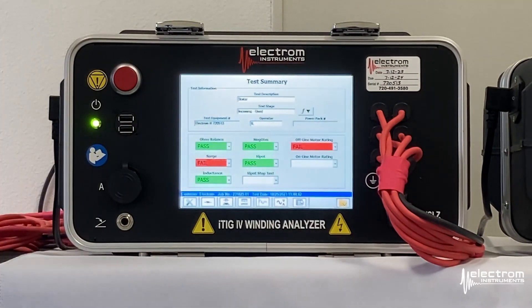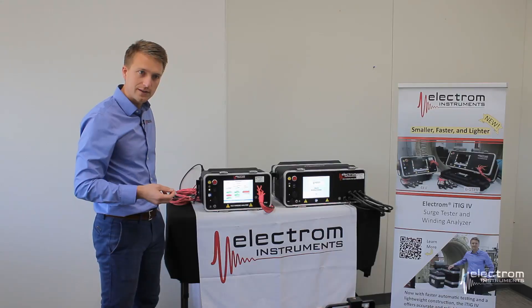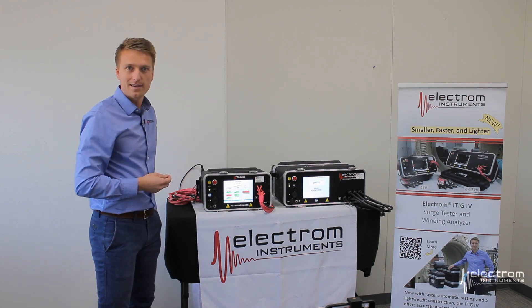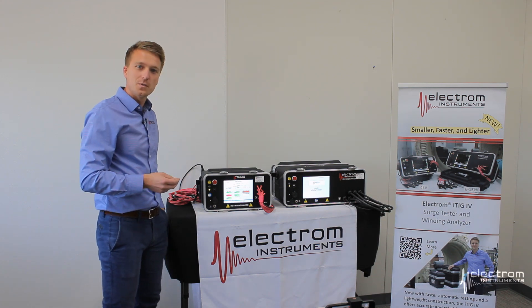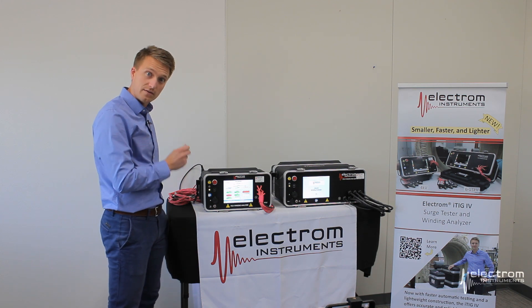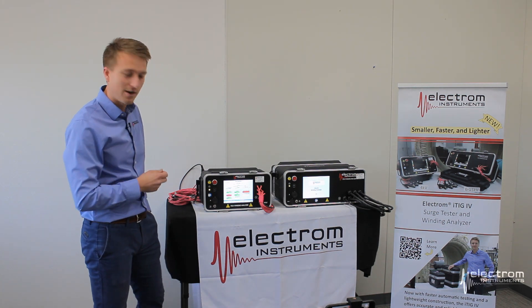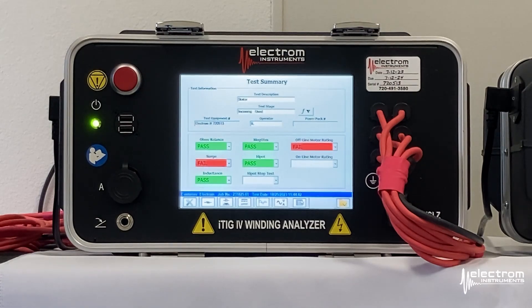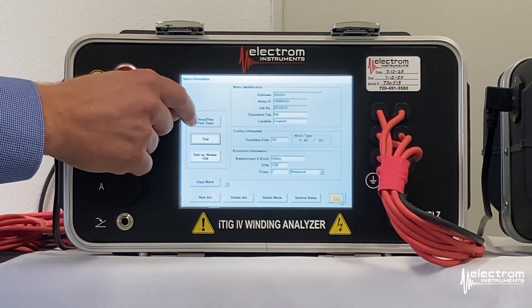At the end of the test set we move to the test summary tab, where we get our pass/fail recommendations. We failed the surge test because the line-to-line comparison between the three phases showed inherent differences — this stator is wound in a way that makes this expected. As a reminder, we would do a pulse-to-pulse surge test to actually verify whether the insulation system is good. When you're done with your test set, click the folder button to exit test mode. Everything is automatically stored — there is no save operation.